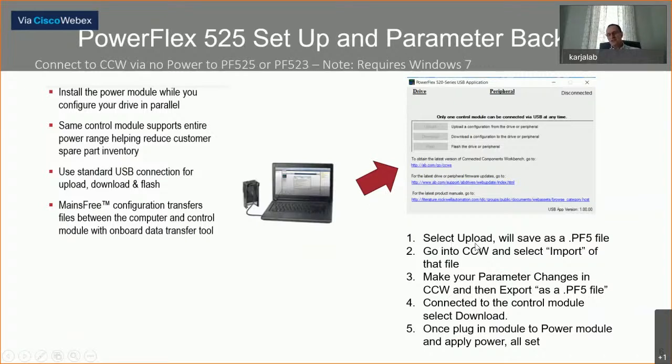For example, I could select upload while in my air-conditioned office with no 480 volt power, plugged in directly like a USB stick. I can save that file as a .PF5 file, then go into Connected Components Workbench and select import to bring in that .PF5 file. I can change everything in CCW, then select export to save it as a .PF5 file again, and do a download to put all the parameter changes back into the control module. Then I unplug it from my laptop, walk to the power module, and it's already programmed.